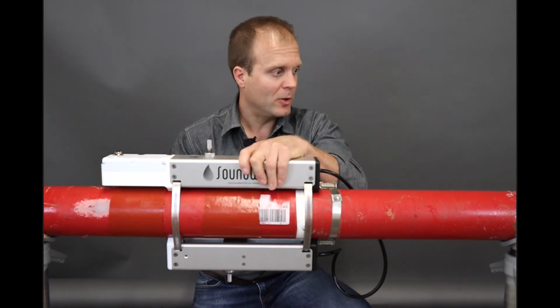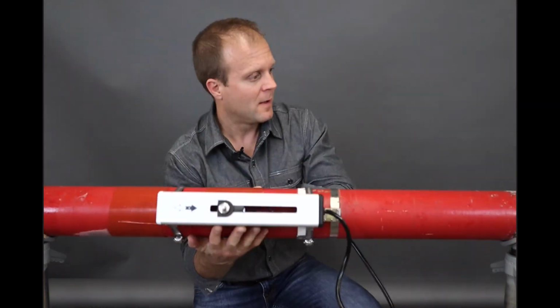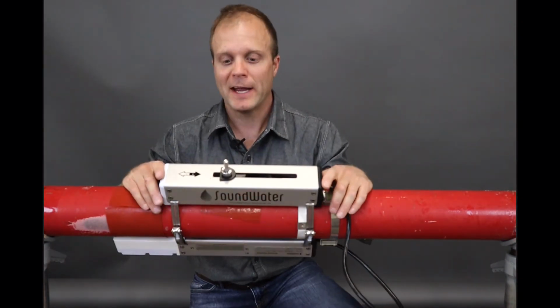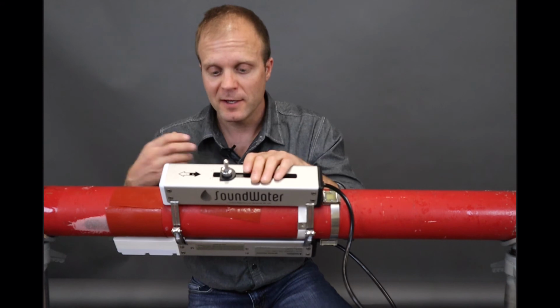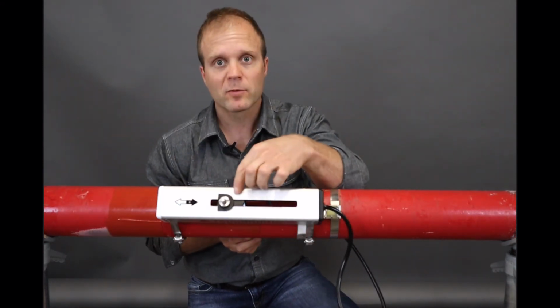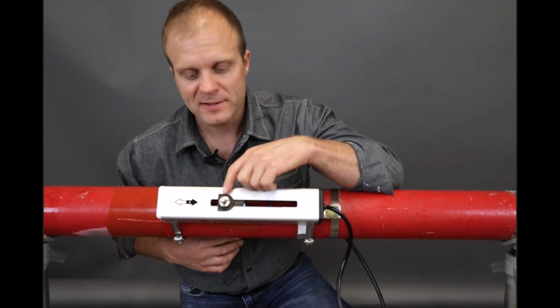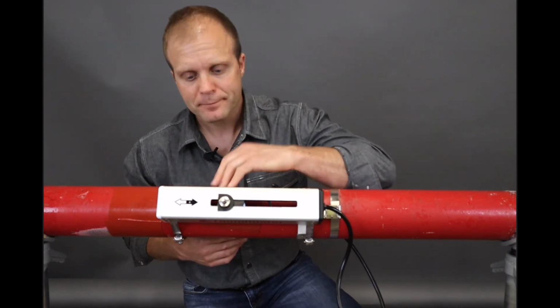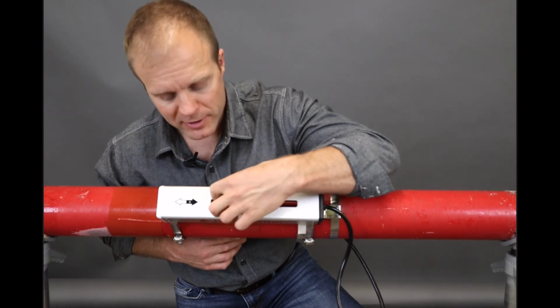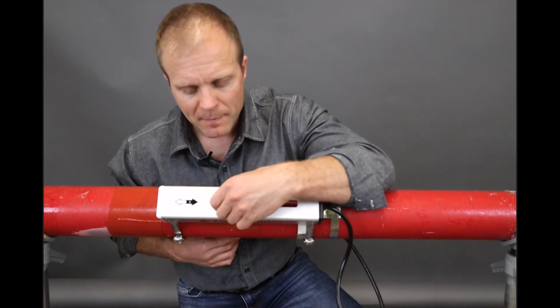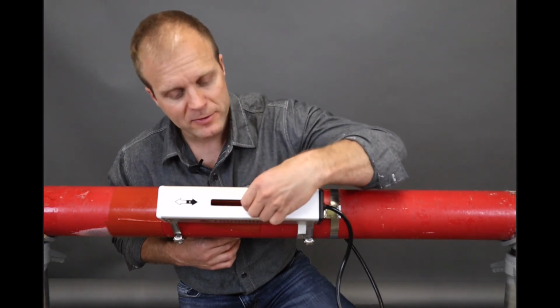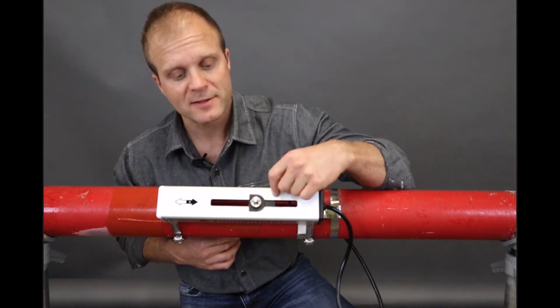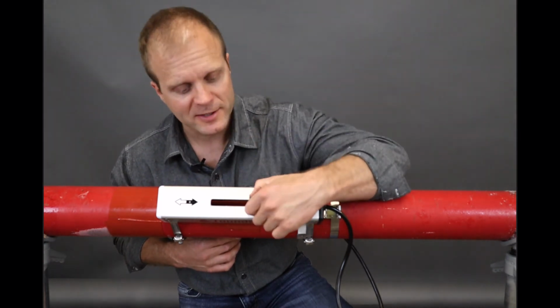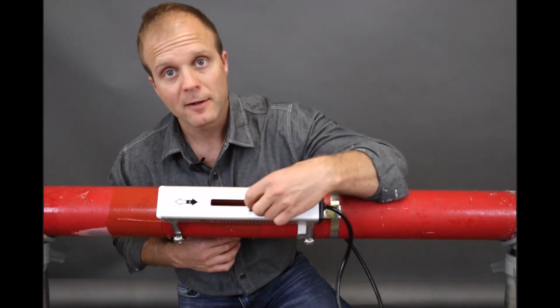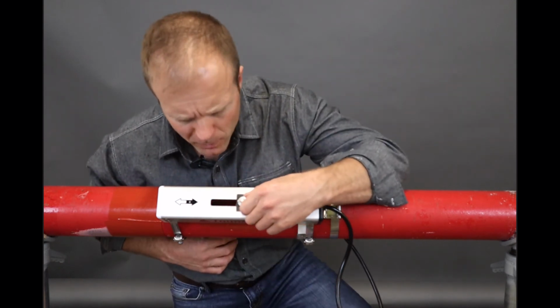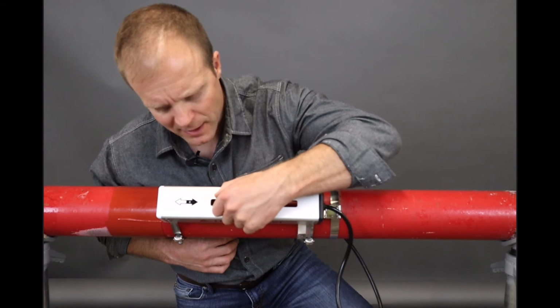You can't move it. So since we're in the studio here, it's easy enough to turn the pipe upside down. Okay, so here is the transducer housing with the ruler on it. So in our app, we set up this 3-inch service line, and it said to put the transducer at 0.4 inches. So this large knob is used to lock the horizontal position of the transducer. So you don't need to turn it a whole bunch, just one little quarter turn, and it unlocks it, and it's free to slide. So we'll just move it to 0.4 inches and lock it back.